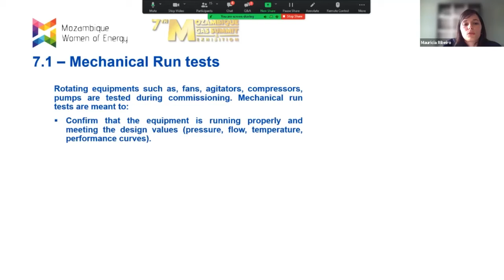Mechanical run tests: all rotating equipment is meant to be tested, including fans, agitators, and compressors. During commissioning, we want to ensure the equipment is properly designed and can run according to the pressure, flow, and temperature it was meant for, and that the pump's performance matches its performance curve.